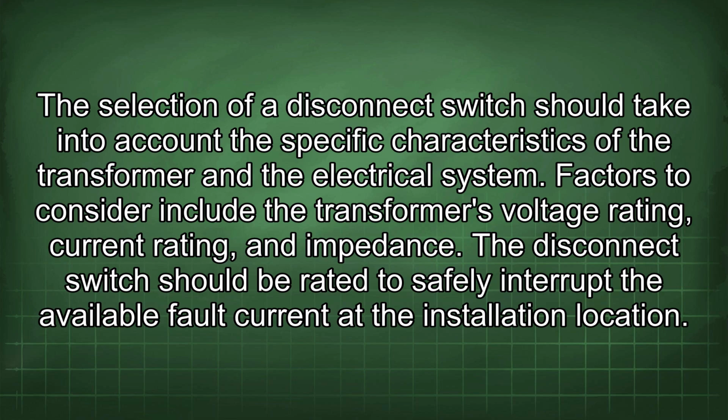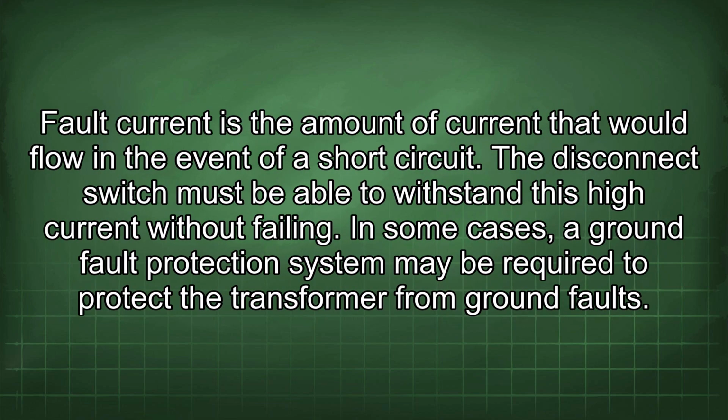Factors to consider include the transformer's voltage rating, current rating, and impedance. The disconnect switch should be rated to safely interrupt the available fault current at the installation location. Fault current is the amount of current that would flow in the event of a short circuit. The disconnect switch must be able to withstand this high current without failing.